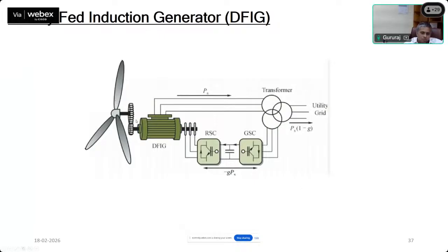So if you see here, the slip ring induction machine, the stator is connected to the grid, and the rotor is connected via the back-to-back converters. Let's say the wind velocity has changed and you're operating at a speed which is less than the synchronous speed. Let's say the synchronous speed of this machine is 1000 rpm, and at 1000 rpm I'll be able to generate 50 hertz that can be directly synchronized with the grid. And wind velocity is not in our control. If wind velocity is down, and because of which the rotor speed is also down, then the speed will be less than 1000 rpm.